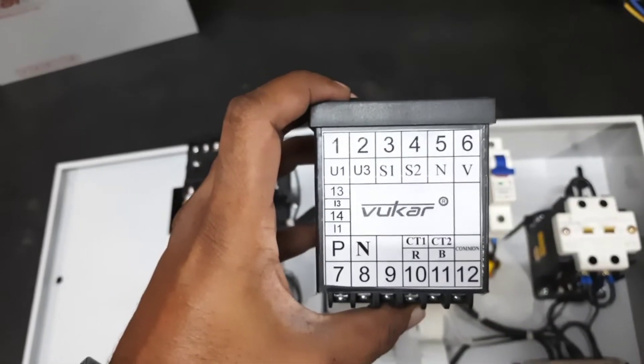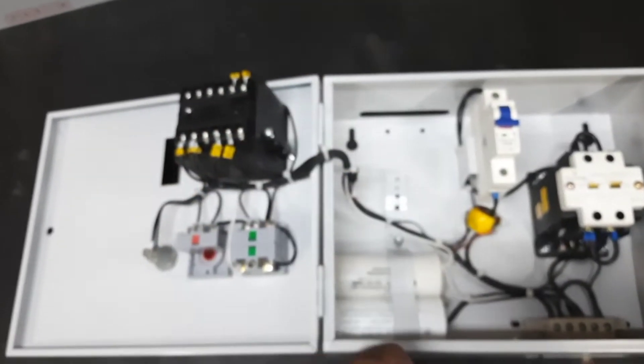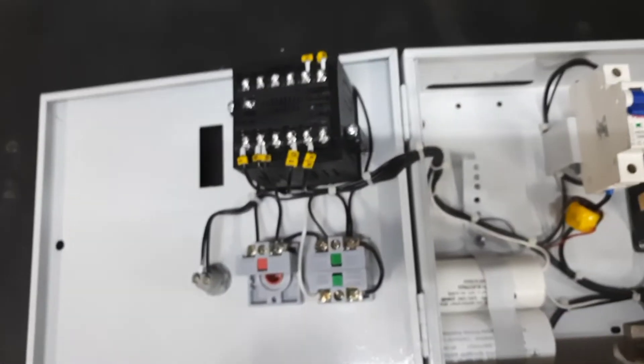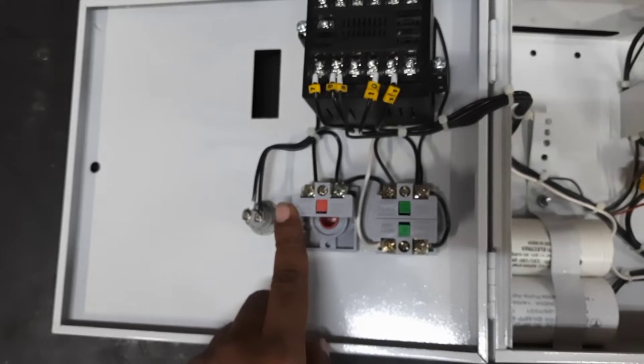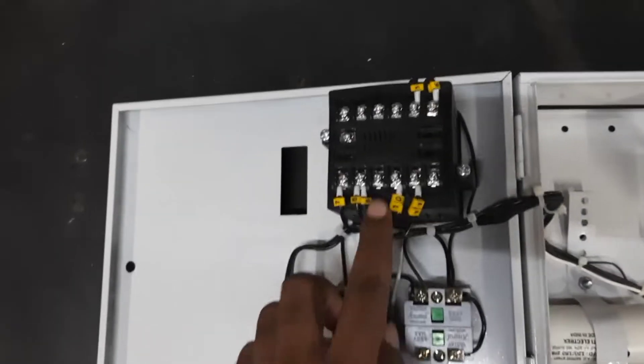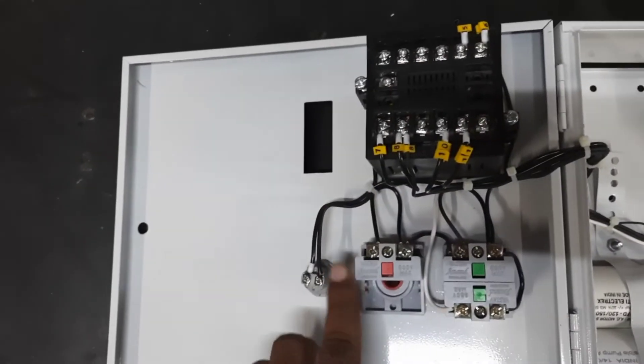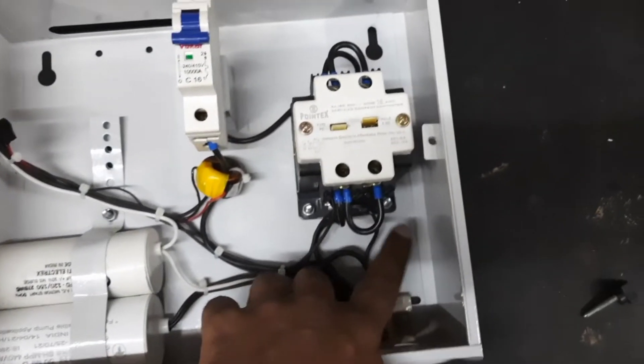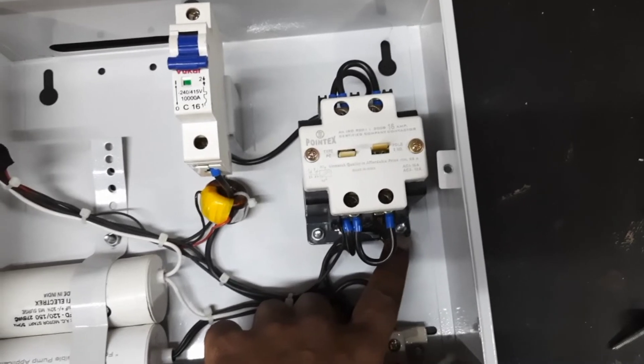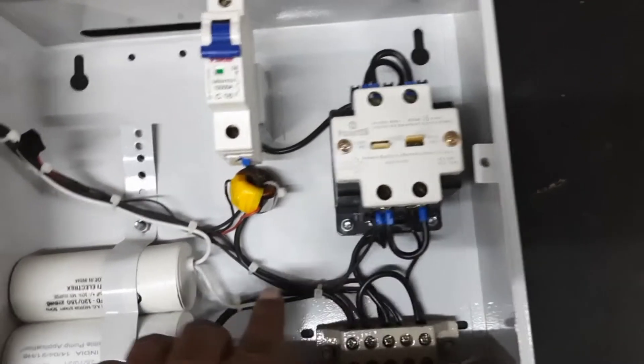Terminals five and six, that is N and V terminal. These will be connected with the off push button and contactor coil. Terminal five is connected with the off push button, and terminal six is connected with the contactor coil. The second terminal of the contactor coil will be directly provided with the neutral.